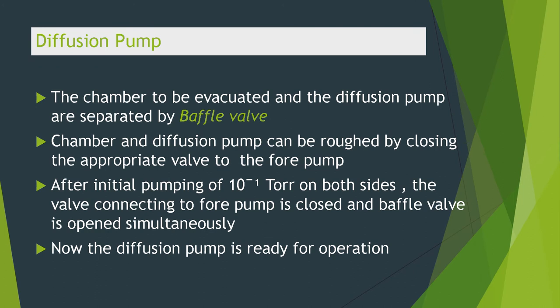The chamber to be evacuated and the diffusion pump are separated by a baffle valve. The chamber and diffusion pump can be roughed by closing the appropriate valve to the fore pump. After the initial pumping reaches 10⁻¹ Torr on both sides, the valve connecting to the fore pump is closed and the baffle valve is opened simultaneously.